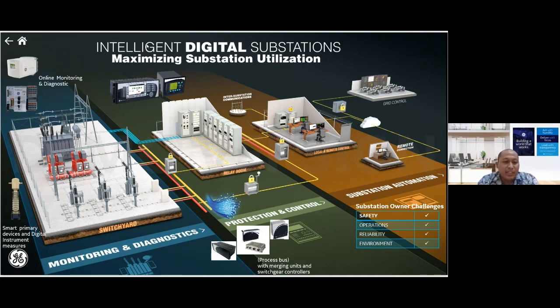Meanwhile, for the digital substation application, the function of current and voltage sensing, where before we were still detecting the current and voltage, is now converted into data. For example, like we have here, the instrument transformer device can now be changed from the conventional one to a digital one. From this digital instrument transformer, it can be used to do sensing of the current and voltage. It will be wired up to the relay inside the control and protection room. But again, the input that we take from this instrument transformer is no longer current or voltage, but is already converted into data.